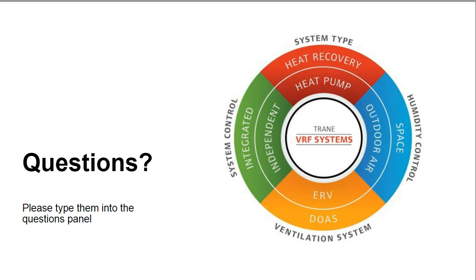Awesome. Okay, so the next question is, if you have an AHU with 2 DX coils, 1 heat and 1 cold, can these be connected to a VRF with heat recovery? Yeah, that is definitely possible. Using the LEV kits for air handler unit operation, those different air handler units can be used with the branch controller of the VRF heat recovery unit to do heating or cooling simultaneously or separately.